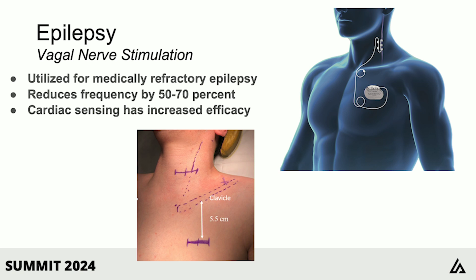There have been some recent advancements with cardiac sensing. So I mentioned with NeuroPace, it listens and it's actually watching EEG readings and then responding whenever it senses something that's abnormal. For this device, it indirectly evaluates for seizures by listening to the heart rate. And when the heart rate increases in a non-physiologic way, that's an indication that a seizure is starting, and then it increases its output and provides burst stimulation, and that does a much better job of helping to control these seizures. And so it's become much more effective with the addition of this technology.